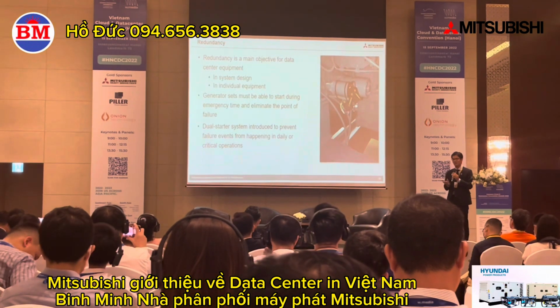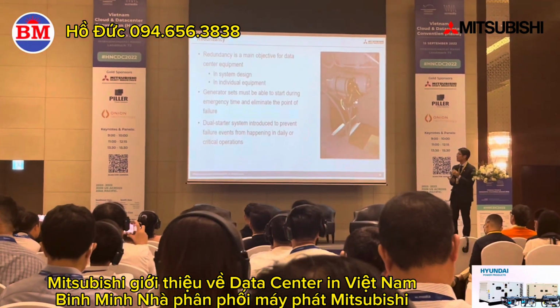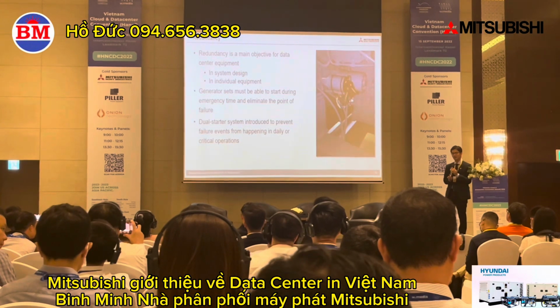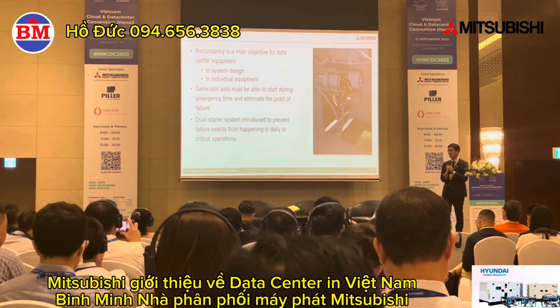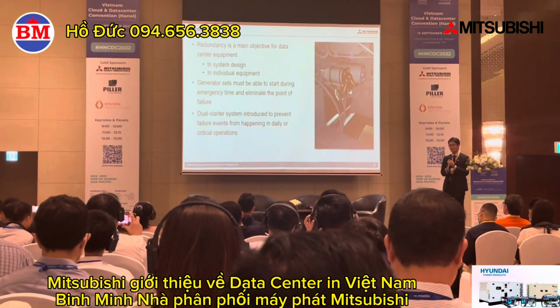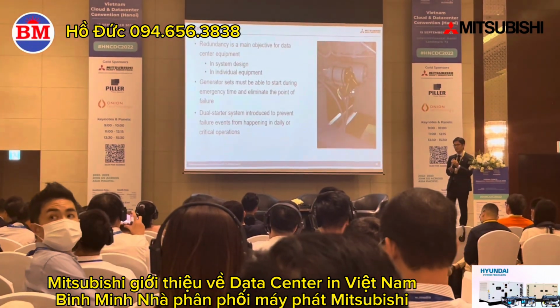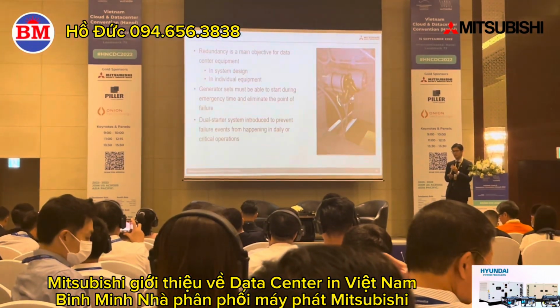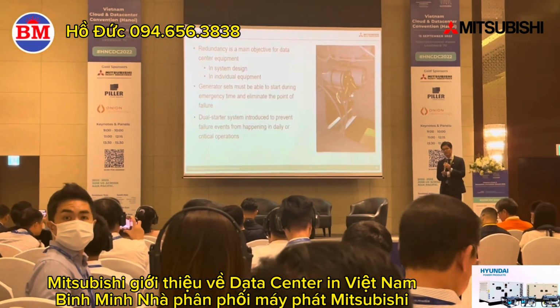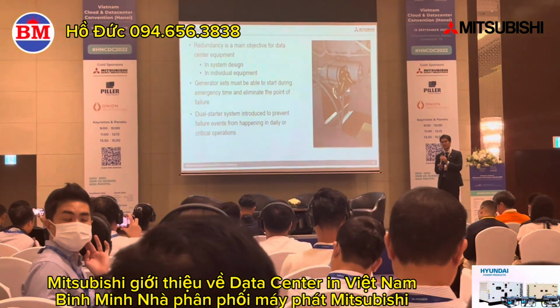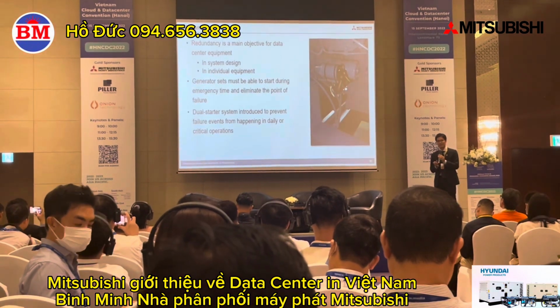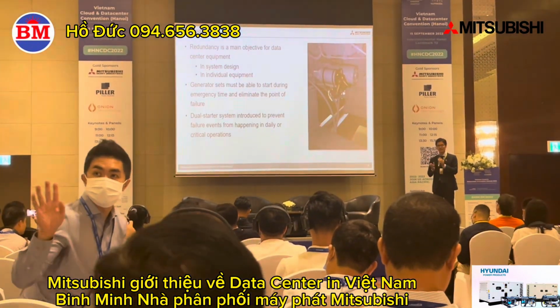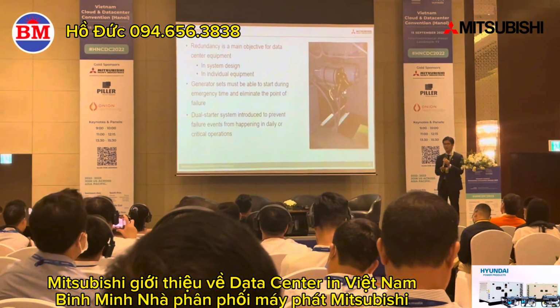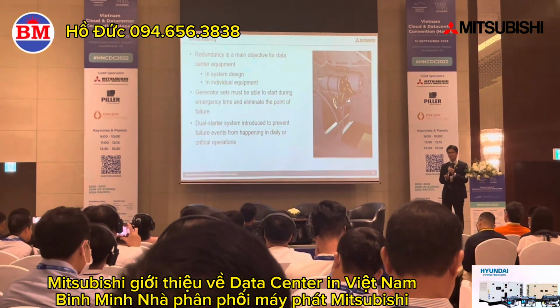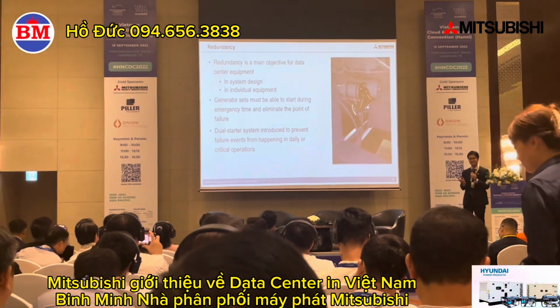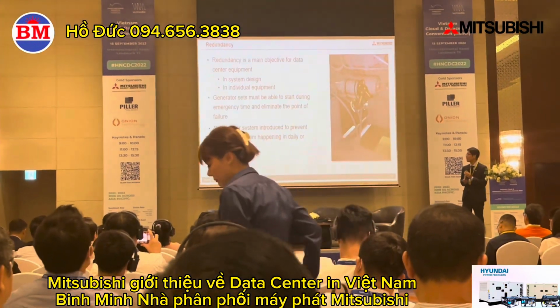Also, for the backup generator in a data center, redundancy becomes very important compared to conventional use of a backup generator. So how to get redundancy is key, and you can get redundancy through system design. If you have an N+1 diesel generator set, you can gain redundancy as a system configuration. However, depending on the customer, there are customers who want to have redundancy in the generator set itself.